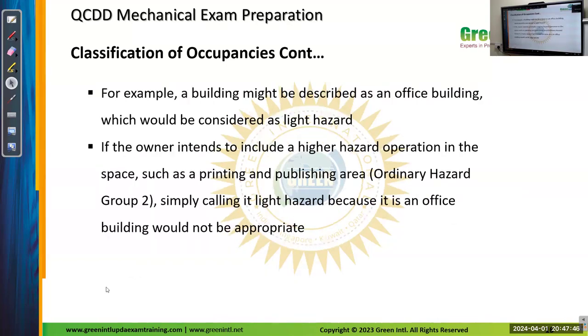For example, a building might be described as an office space, which would be considered a light hazard. If the owner intended to include a higher hazard operation in the space, such as a printing and publishing area, ordinary hazard group 2, simply calling it light hazard because it is an office space would not be appropriate. So what we identified first, and based on which the sprinkler is designed, only that is to be used. If you change to another occupancy level, you have to redesign the sprinkler, and the sprinkler K values and all these steps will change.